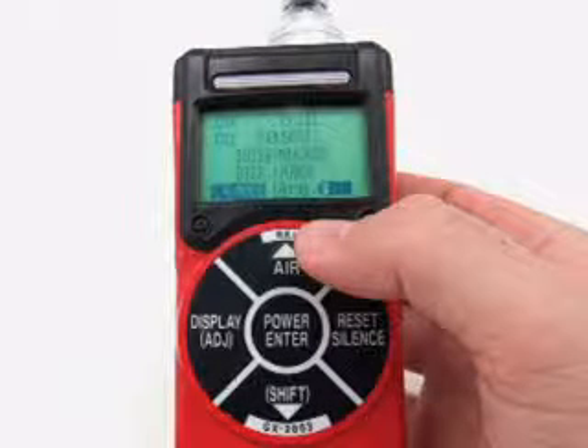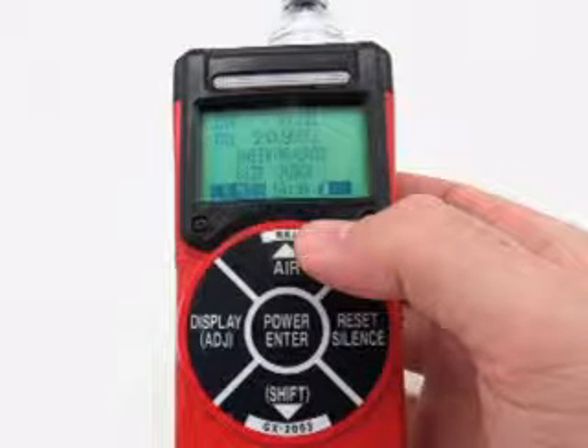The GX2003 is now operating in bar hole mode. The pump is off and the bar hole screen appears. The current methane and oxygen channels are displayed along with the time and battery charge level. Before using the GX2003, it is recommended to set the fresh air readings for the target gases by performing a demand zero. This will set the methane channel to 0 and the oxygen channel to 20.9%.